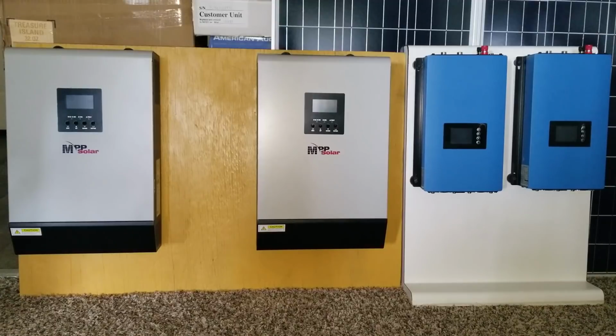The blue ones, no power, it's not going to feed back to the grid at all, because those sensors limit exactly what you supply to the grid, how much is coming out from each line, and that's the power that's gonna supplement back. It puts back there exactly, so that you cannot spin the meter backwards.